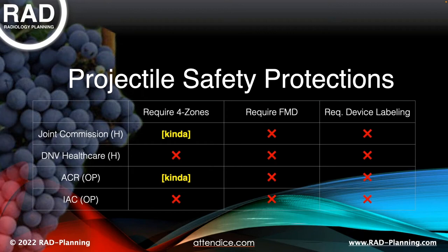ACR, I am being really generous in giving them a kinda in 4 zones. So ACR developed the 4 zones. Each and every one of these safety principles comes directly from the ACR's MRI safety best practice document. ACR requires, I'm going to goof up the specific language, but it's something like appropriate access controls. So they do mention that there should be some kind of access control as you approach the MRI. They don't describe where that should be, how that should function, or how that relates to screening or supervision or any of those things. So I'm being super generous, giving them a kinda for that one. IAC, like DNV, they strike out across the board for this.